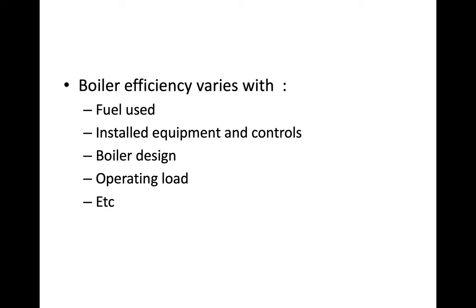The fourth one is that boiler efficiency also depends on operating load. Mostly, boiler efficiency is higher at full load, and efficiency decreases with the decreasing of the load. At low load, the boiler's efficiency tends to decrease.